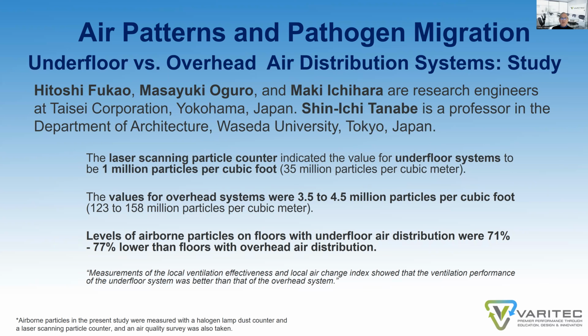What they found using laser scanners and particle counters is that in the underfloor air system, a building conditioned by underfloor air, the contaminant density read 1 million particles per cubic foot. However, in the overhead system, they registered a particle count of 3.5 to 4.5 million particles per cubic foot. Consequently, they came to the final conclusion that levels of airborne particles on floors with underfloor air distribution were 71% to 77% lower than floors with overhead air distribution.